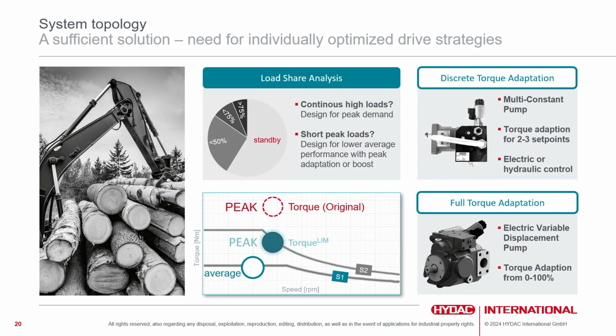The next point is also very important. It's not only about efficiency, it's also about having the right strategy in operating your functions, so that you can make a proper design, for example, of the motor and the whole drive system. So it's very important to analyze the load cycles, for example with the load share analysis chart you see right here. You check how often the system is in standby, how often it operates in a middle range, or in the peak level. What we could see in this machine is that for that dedicated use case, they were very often in standby mode, and peak demand only occurred very seldom, in this small little black pie piece you see right here.